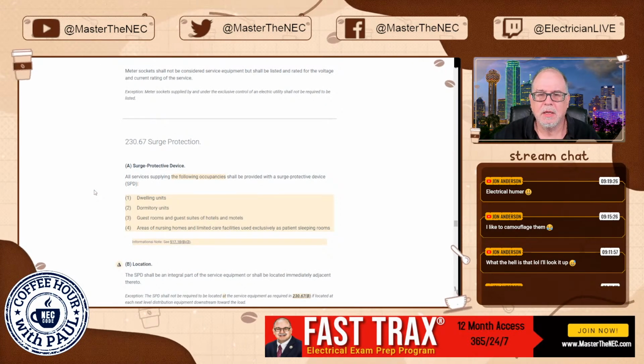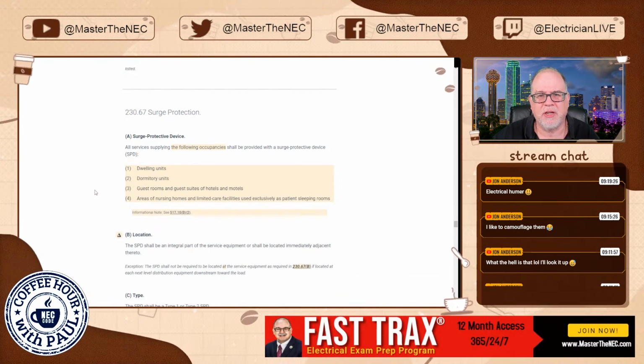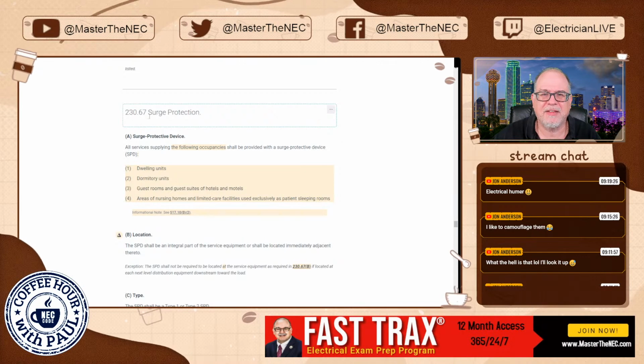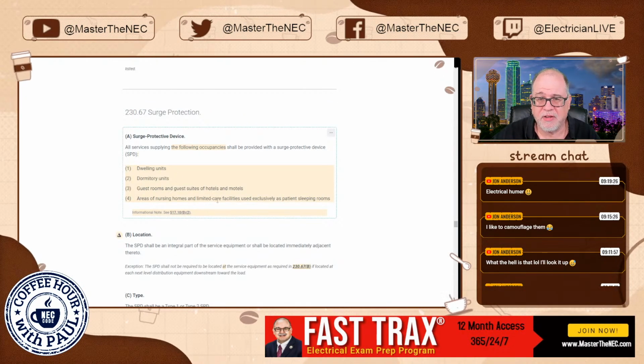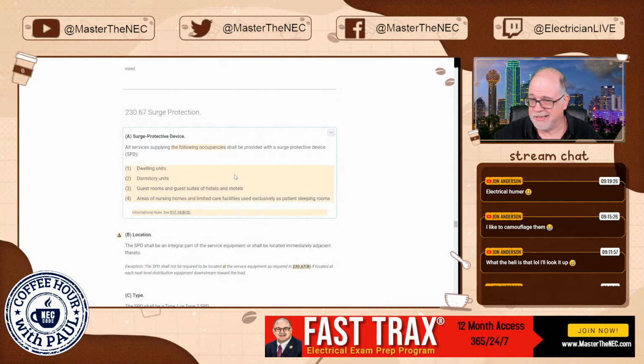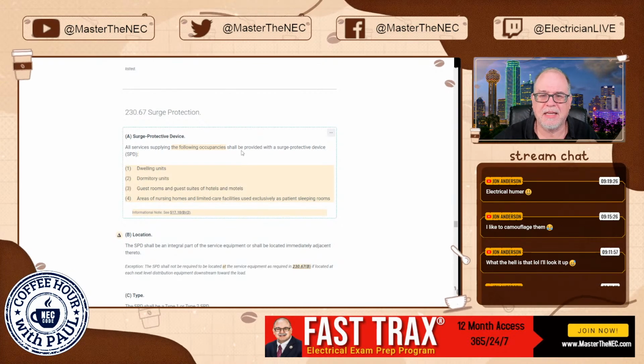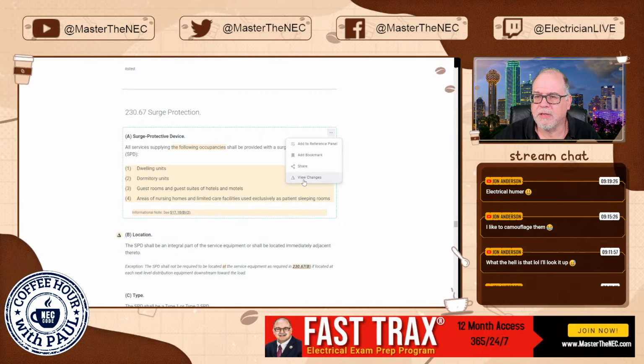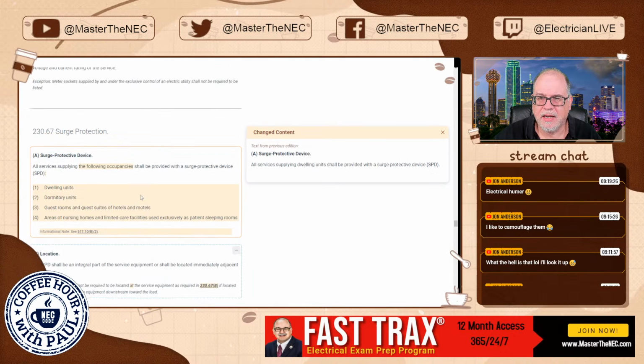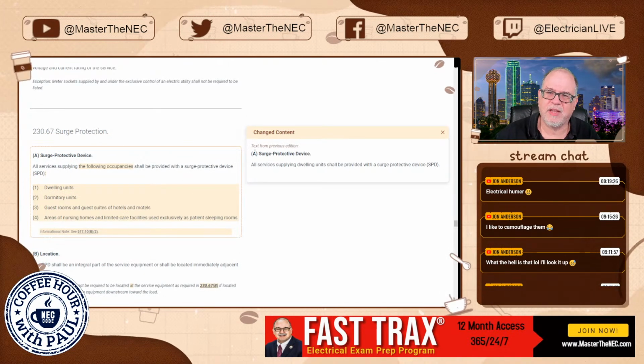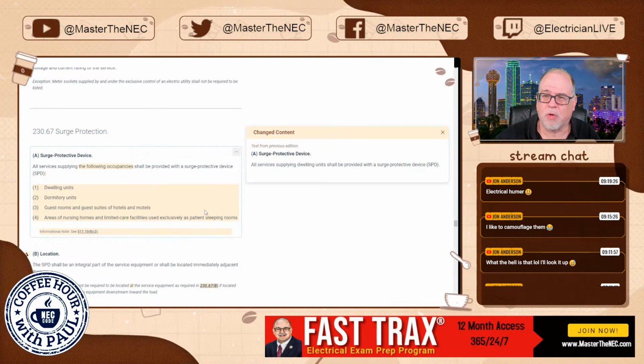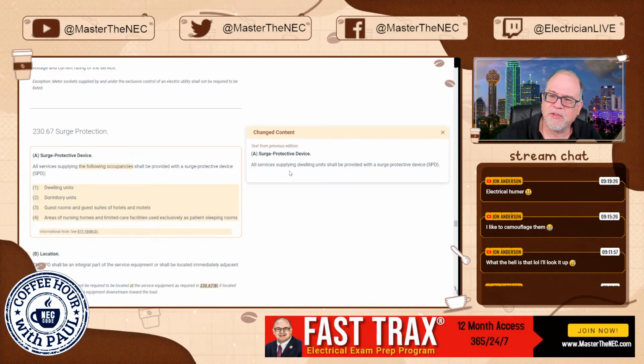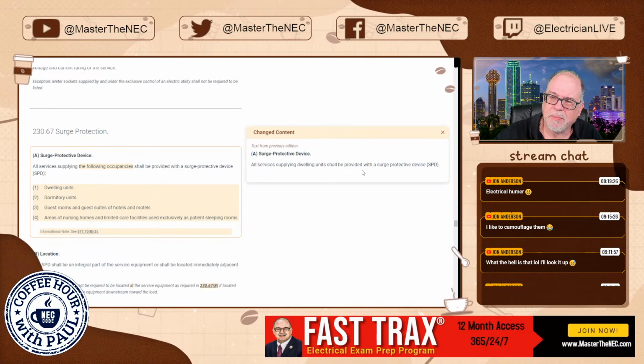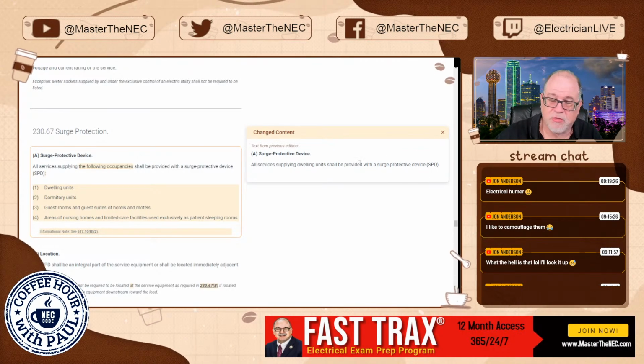All right, surge protection, okay, 230.67. This, again, is not new. This was in the 2020 edition of the NEC. And as you can see here, what it said in the 2020 edition on the right was, all services supplying dwelling units shall be provided with surge protective devices. Okay, that was 2020.